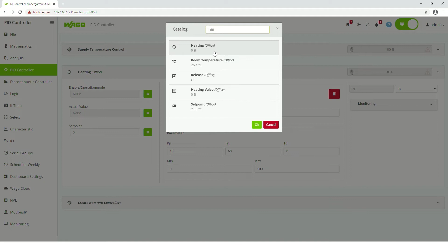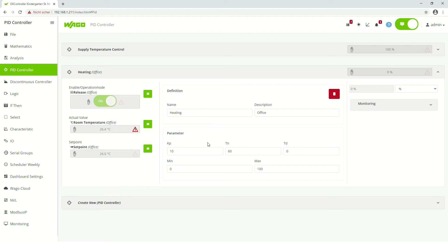So I could assign here the release signal to the PID controller, the actual value, the room temperature, the set point. Now the last step is to connect the output of the PID controller to the heating valve.